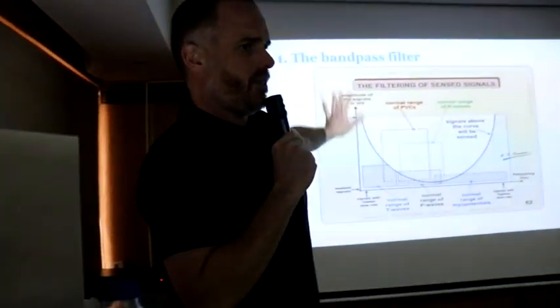So sometimes I tell them, don't trust what we see now, because some values are not measured in the wiring of the system, but sometimes you are obliged to use this machine in order to have crude measurements of the signals. The problem is with the atrial signal because it's very little, and the accuracy is not that correct. And those differences in size when using a temporary box are because the bandpass filter is completely different to what we're doing on the device. So that's why I talked about that.